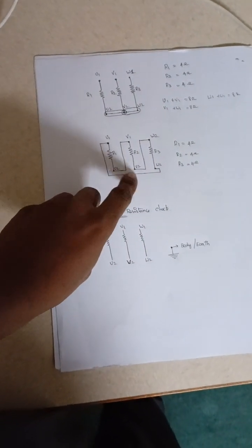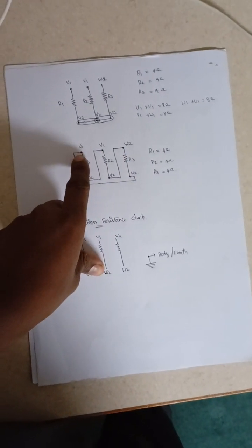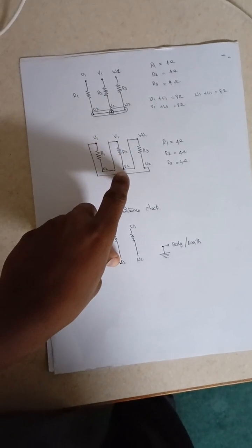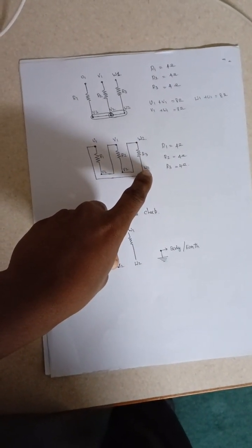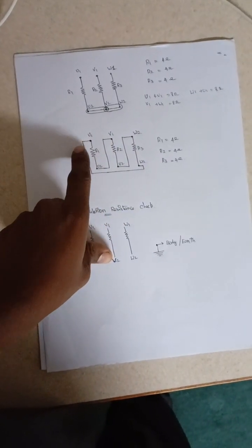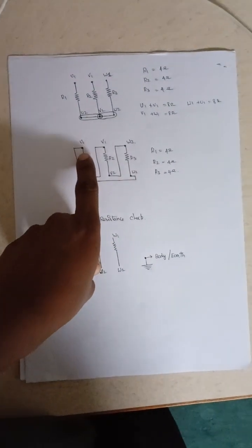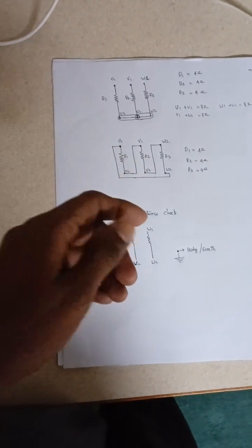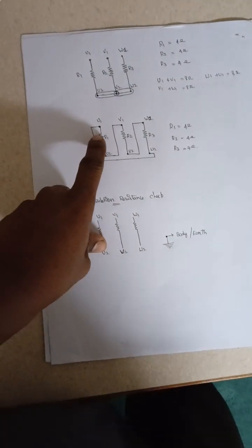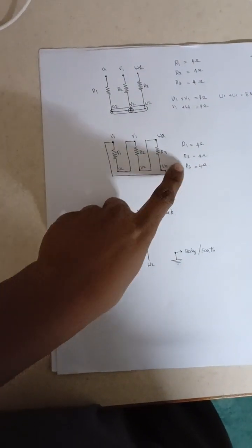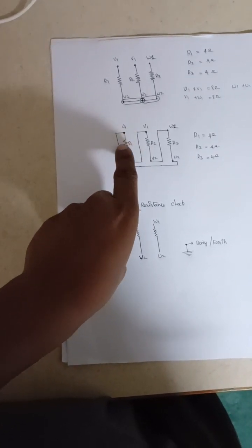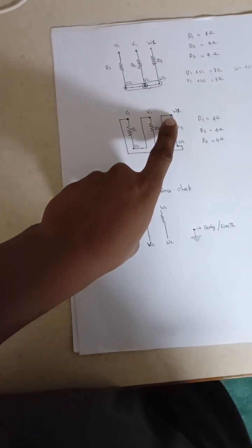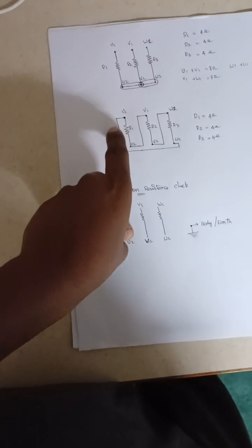See, in the delta connection you will get a normal resistance. When the motor is connected in delta, you can find that U2 is connected to V1, V2 is connected to W1, and W2 is connected to U1. So once we measure the resistance, we will usually get 4 ohms between U1 and V1 because it is connected in delta, and between V1 and W1 we will get only 4 ohms. Between W1 and U1 we will also get only 4 ohms.